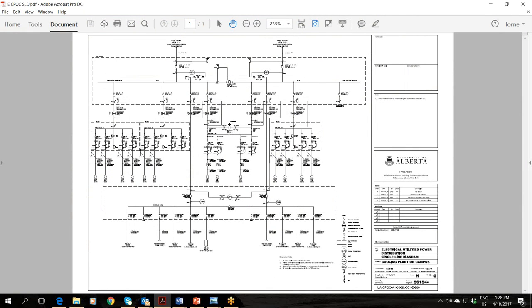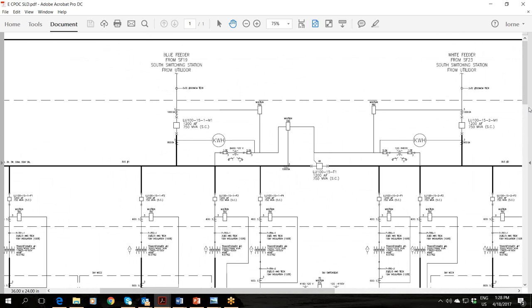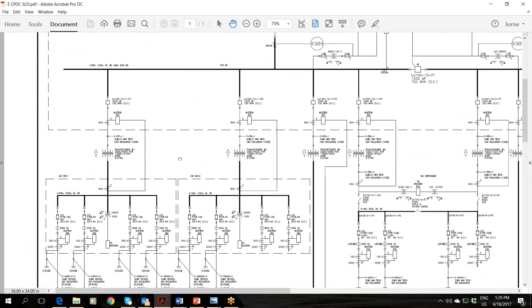So we have several different plants I talked about a little bit already. This is the single line for our second cooling plant, that was more recently built in 2010, the cooling plant on campus. So again, we've got a main tie main arrangement. This is a direct supply from the south switching station. So there's two breakers, one on bus 1, one on bus 3, that feed down into this 15 kV lineup, which is in the cooling plant on campus building. Again, tie open, mains closed. We don't do automatic transfer at the medium voltage level. Everything at the medium voltage level is manual transfer, either remotely or locally, but ultimately manual transfer.